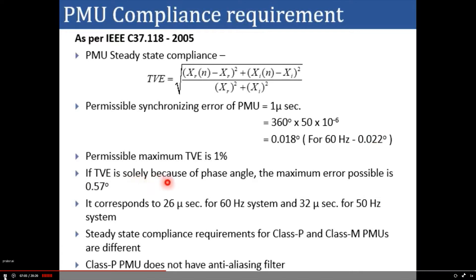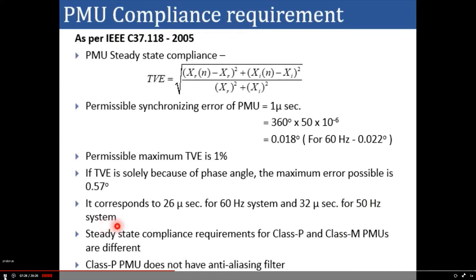If the total vector error is solely due to phase angle, the maximum error possible is 0.57 degrees. Translating into time, the maximum error is 26 microseconds for a 60 Hz system and 32 microseconds for a 50 Hz system.